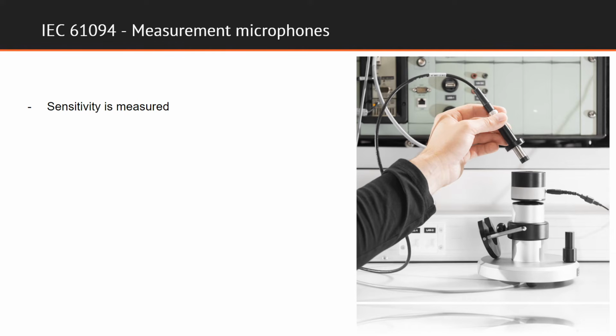The sensitivity of the microphone being calibrated is measured by comparison with the reference microphone. The two microphones are exposed to the same sound pressure in an active comparison coupler, which contains a built-in sound source. The measurement frequency can be set to either 250 Hz or 1000 Hz.